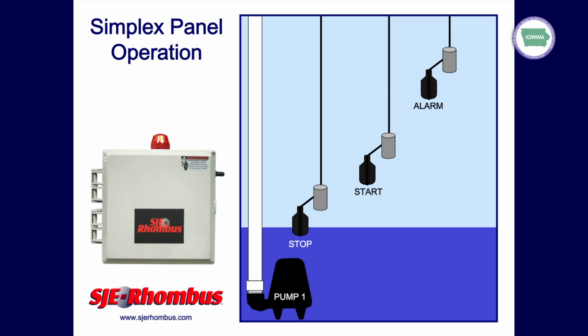All right, when we do the installation of the floats, this is one setup here where, if you look up at the top of the tank, we would have a float bracket, and we have our floats hanging down. When I mentioned the cable weights with our 3.5 inches of tether, that's what I was talking about. Normal operation for the floats for a single pump application and a control panel typically is going to be 3 floats, where you're going to have a stop float, a start float, and an alarm float.